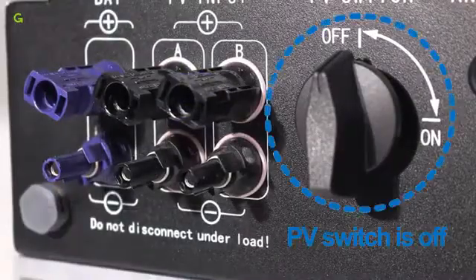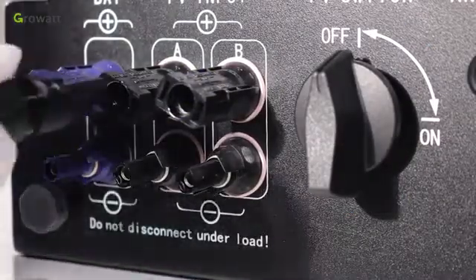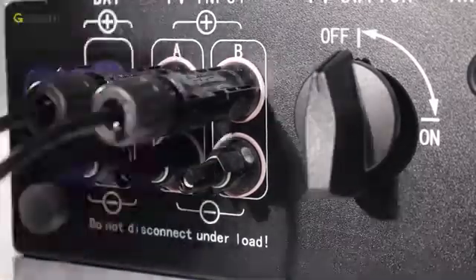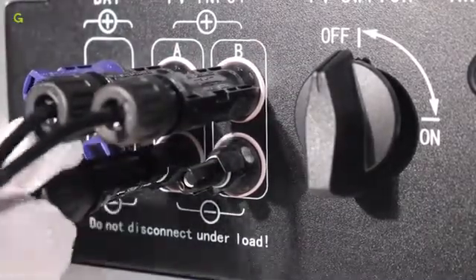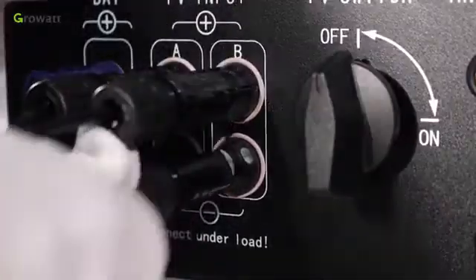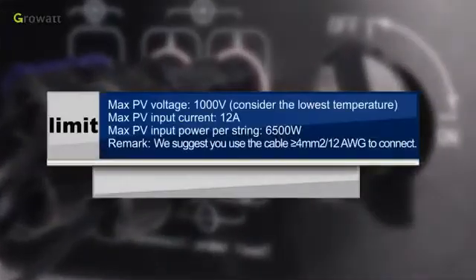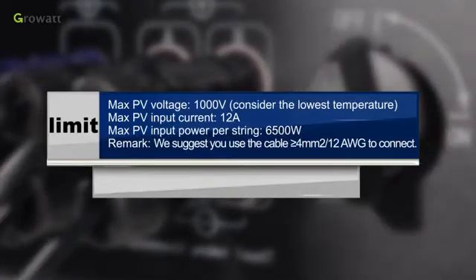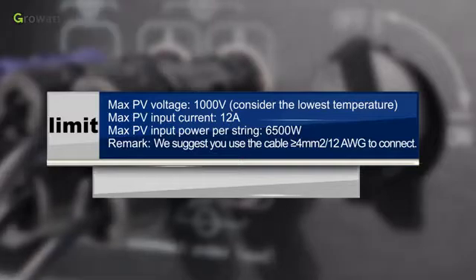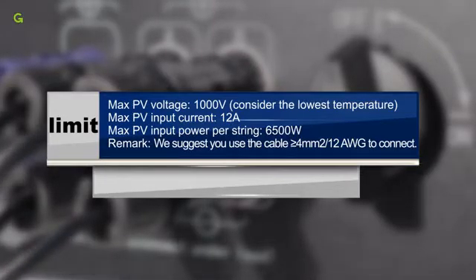Make sure the PV switch is off. Similar to the traditional inverter connection, the input of the PV panel can be realized by using the PV terminal. Insert PV panel positive and negative cables into the relative terminal of the SPH. Limits: maximum PV voltage 1000 volts, maximum PV input current 12 amperes, maximum PV input power per string 6,500 watts. We suggest using cable greater than 4 square millimeters (12 AWG) to connect.